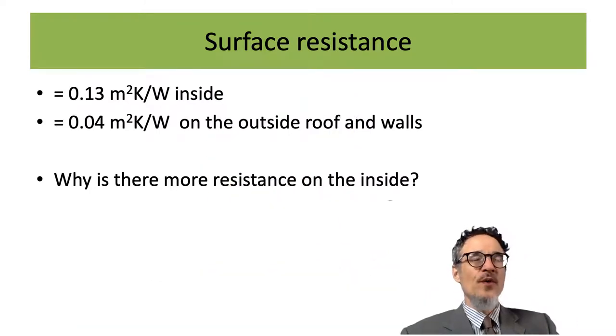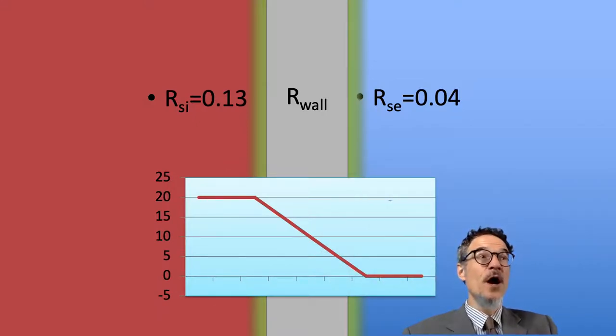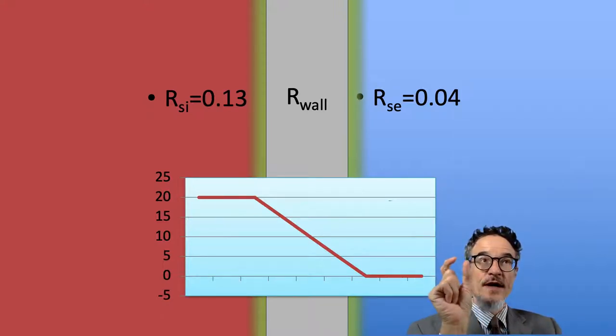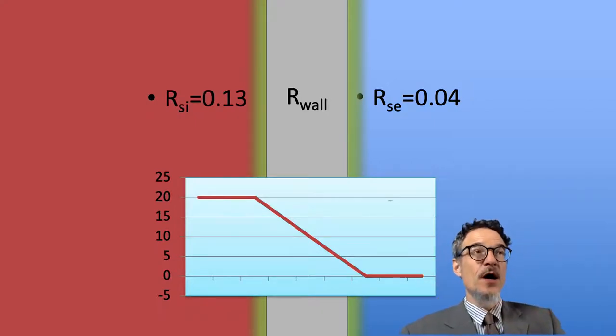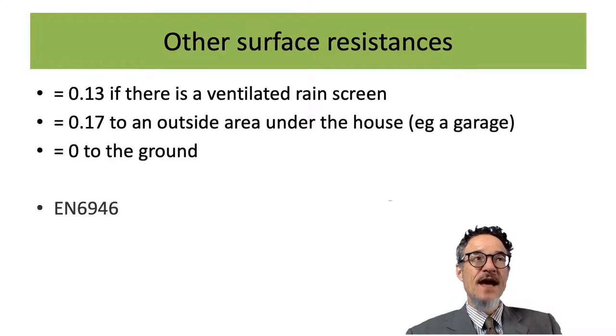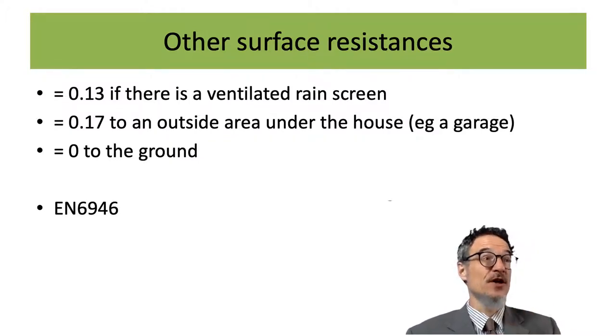If we have a real wall — thicker than paper with some R-value — we have three layers: the inside surface resistance, the wall itself, and the outside surface resistance. We add up these resistances. If there's a ventilated rain screen the resistance is slightly better; if the house is on the ground there's no surface resistance and heat will conduct directly. There are slightly different surface resistances for different situations.